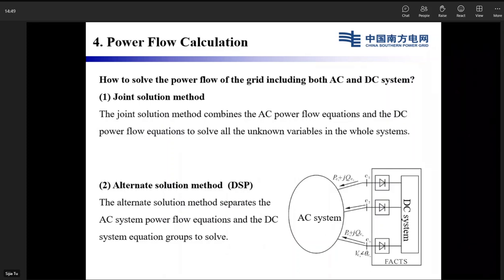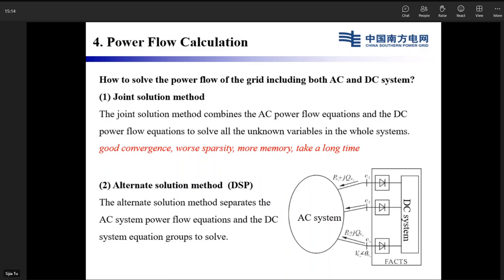In the DSP, we can calculate the power flow in the grid, including both AC and DC systems. The traditional method to solve this system is the joint solution method, which combines the AC and DC power flow equations to solve the whole system. It can easily converge, but needs more memory and takes a long time. In DSP, we use the alternate solution method instead: we separate the system into AC and DC parts, which have connections through an interface. It is flexible, but has worse convergence.